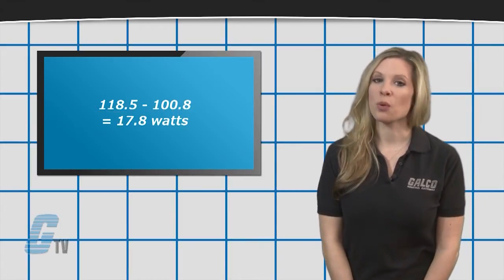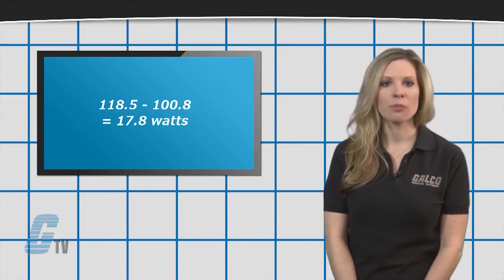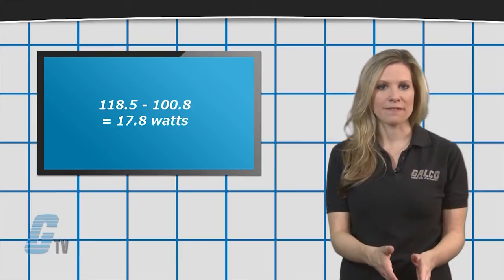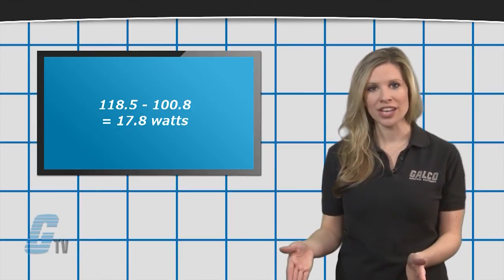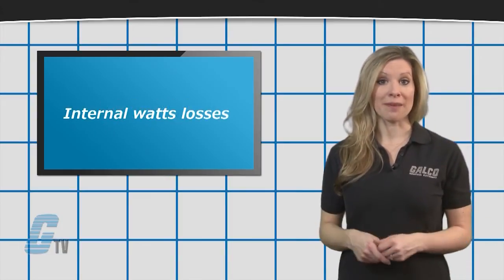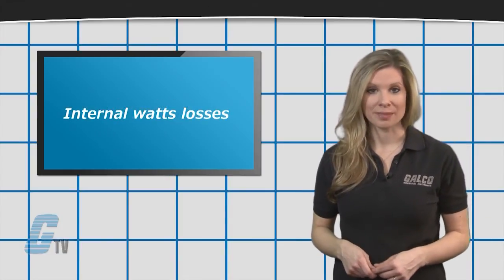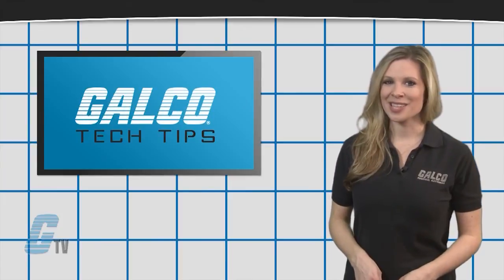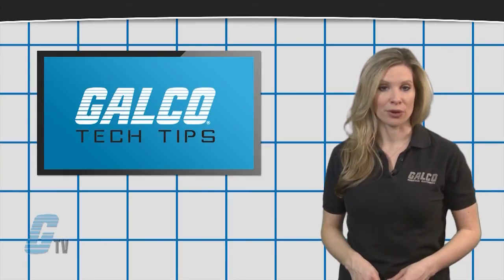Now I will subtract the 100.8 watts from the 118.5 watts I just found to get a value of 17.8 watts. This would be my internal watts losses. This will help in sizing the appropriate cooling method for your device.